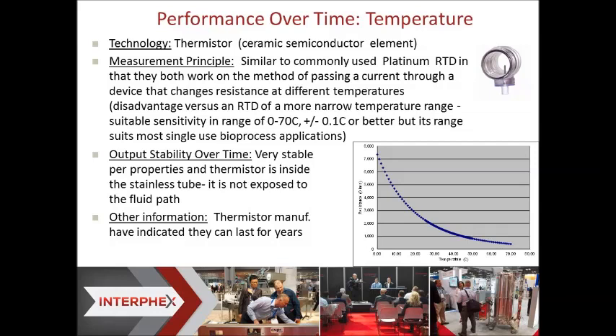The temperature element in our temperature sensor is called a thermistor. It's a semiconductor element, and it's very similar to an RTD, which measures a current being passed through, which changes resistance versus temperature. The disadvantage of a thermistor versus an RTD is its more narrow temperature range. If you look at the graph here, 0 to 70, above 70 there's not much change in resistance versus temperature, but most single-use applications are not going to be above 37 to 50 degrees. So it's very stable over time, and our thermistor manufacturers indicate they can last for many years. And the thermistor itself is protected. It's within the tip of this stainless steel sheath, so the thermistor itself is not exposed to any chemicals.